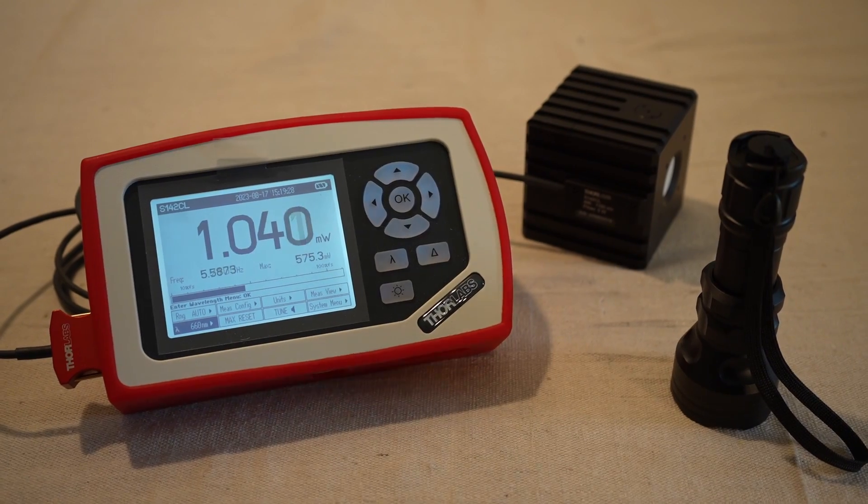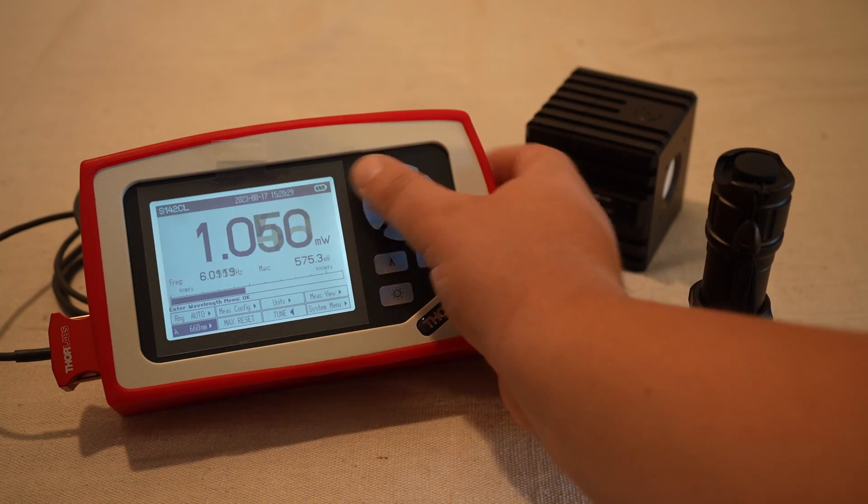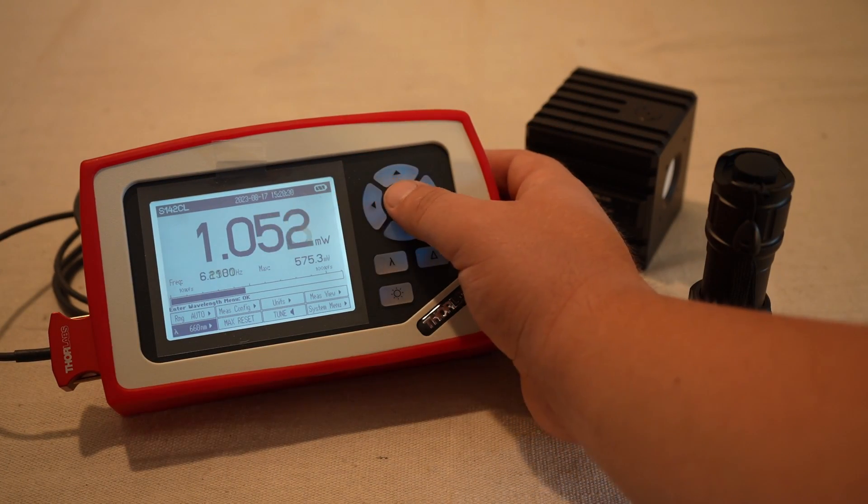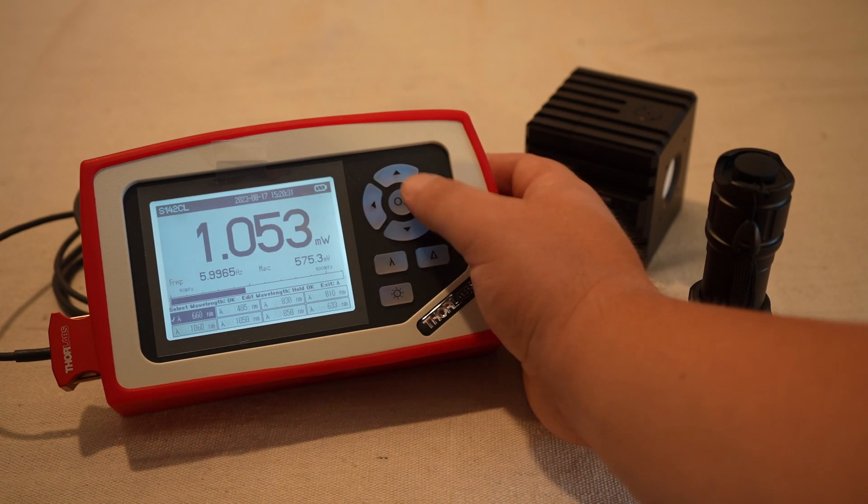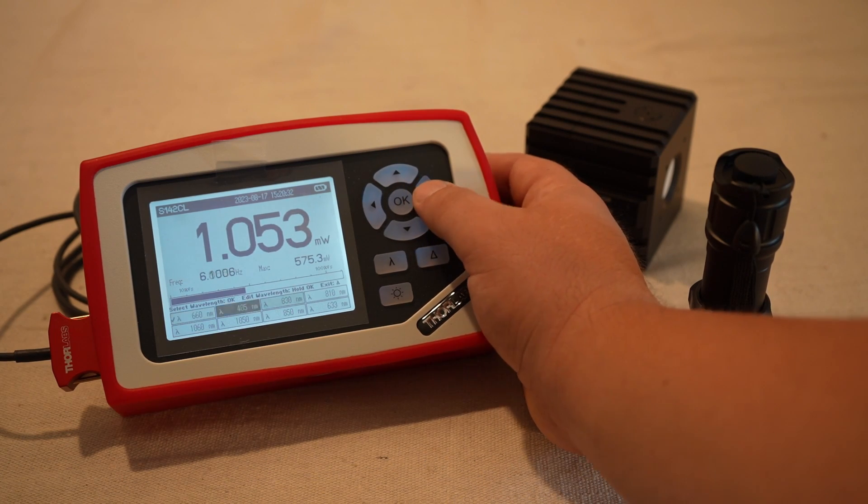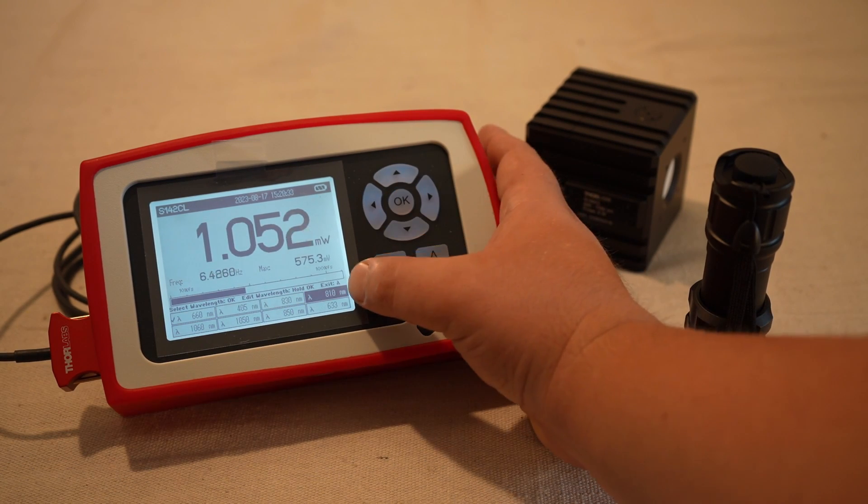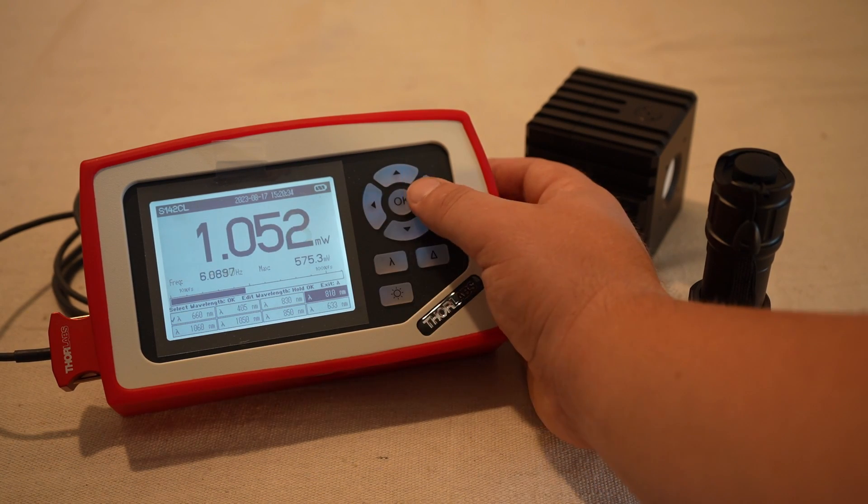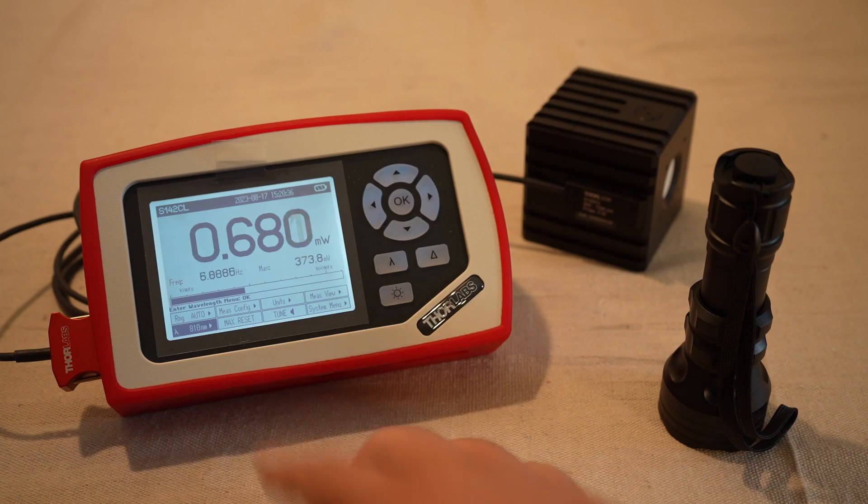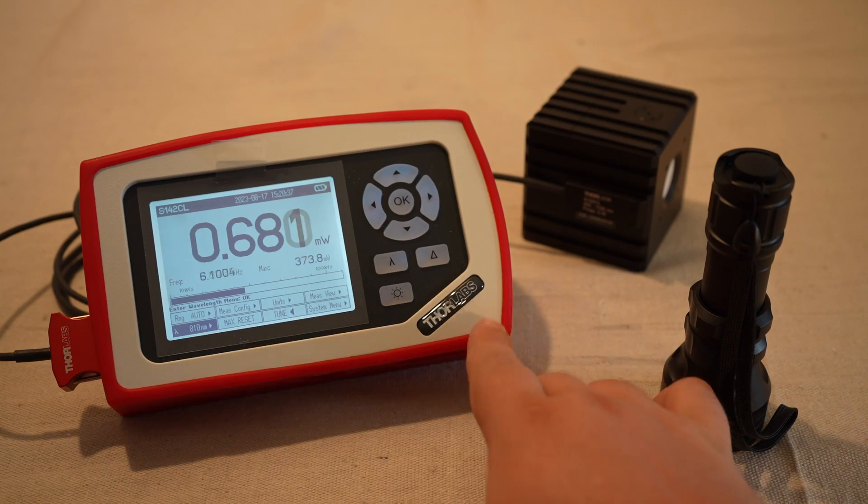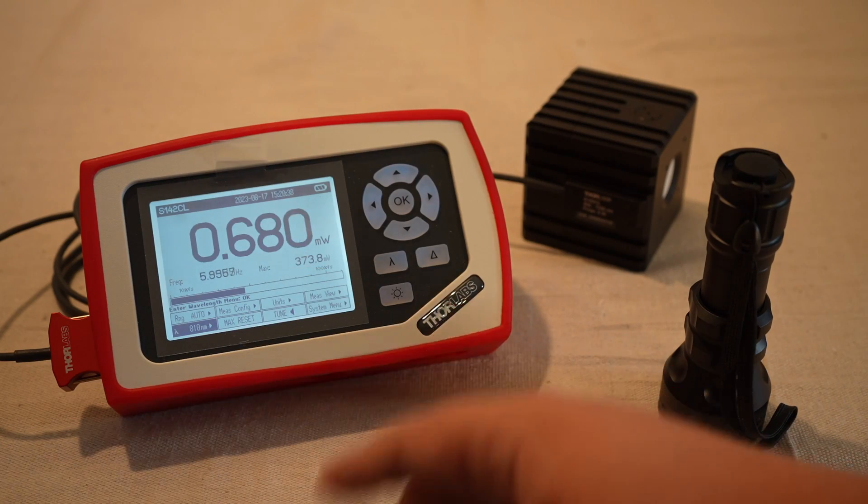Okay, first thing we'll check, make sure our wavelength setting is right. So we're going to set it to the 810 nanometer wavelength, because even for high quality optical power meters, there might be a sensitivity curve.